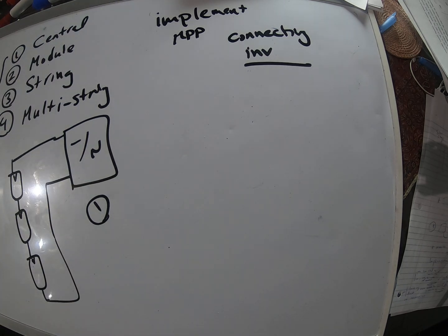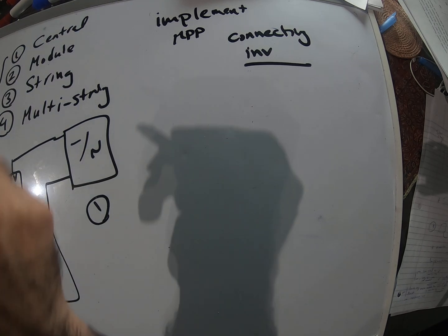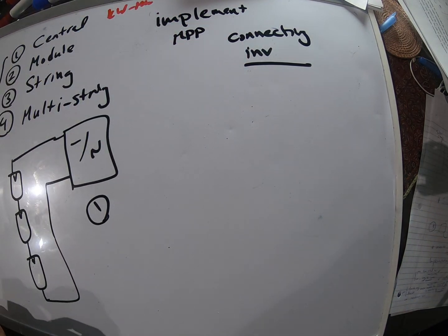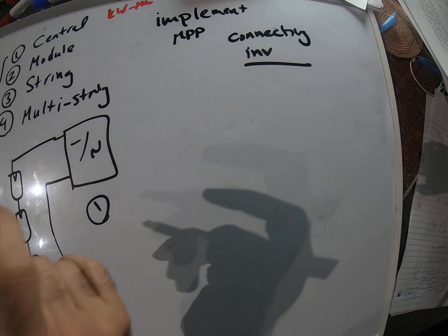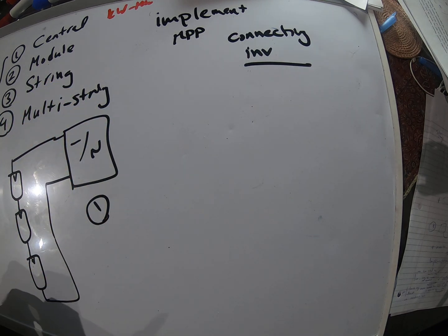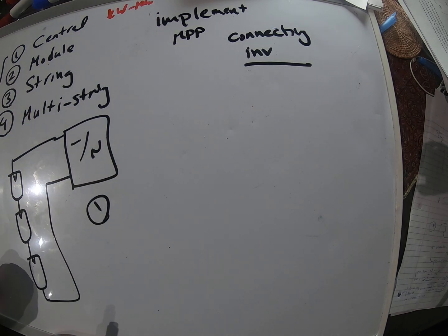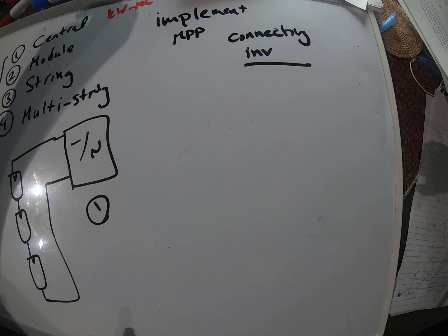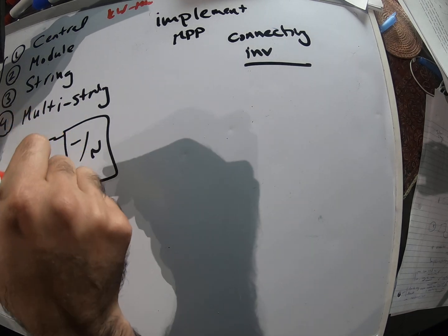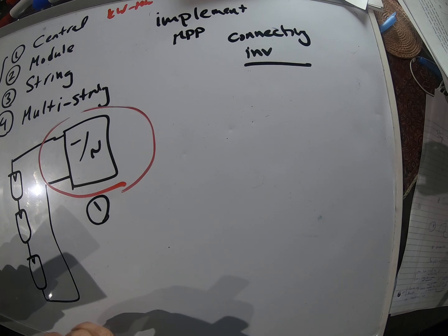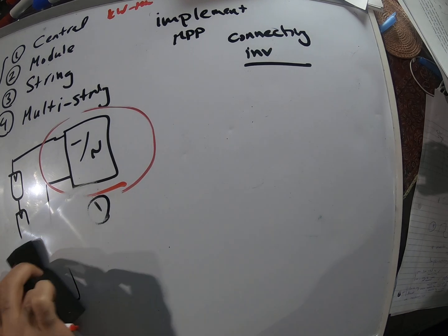It's usually used in very high power applications, let's say kilowatt to megawatt. Okay, so this is the central, and the MPPT algorithm is implemented in this inverter. It tries to adjust the voltage. You might also have a DC-DC converter here, so you adjust the voltage in this power electronic interface to get to the maximum power point.